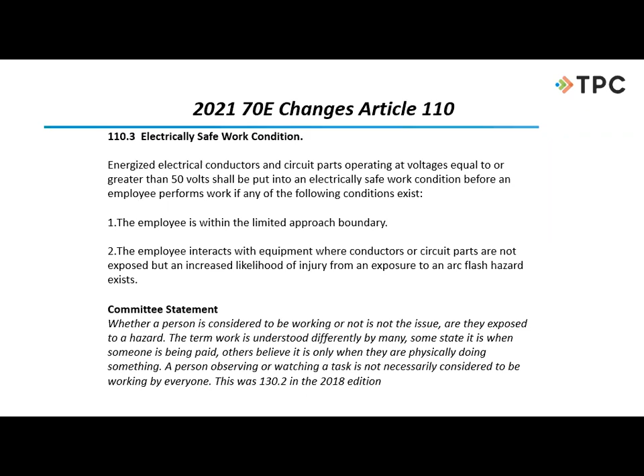There was an issue about what counts as 'working on it.' A lot of people believed it would only apply if the person was being paid, or that if somebody was just standing by observing, that's not work, so they wouldn't have to establish an electrically safe work condition. But that's not the case - they believe that if we are inside that boundary for any reason whatsoever, we need to establish that electrically safe work condition. So, a little bit of change here about the electrical safety program.